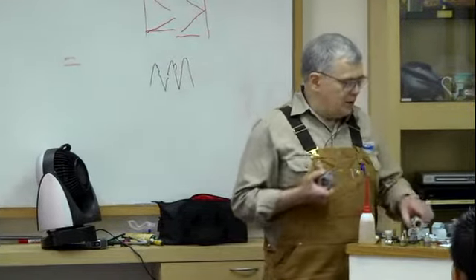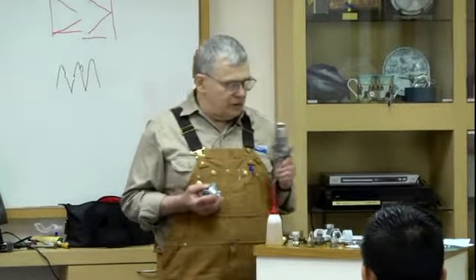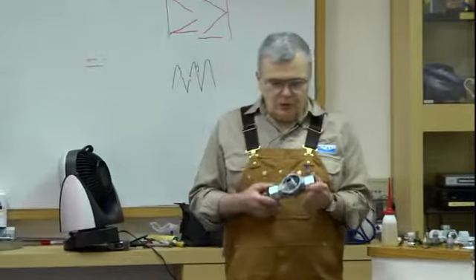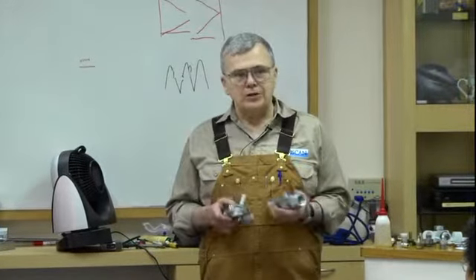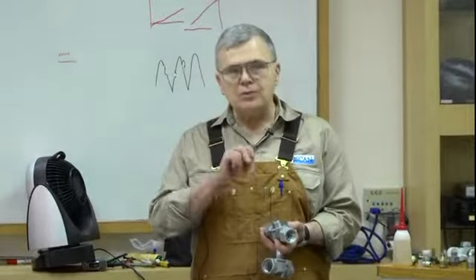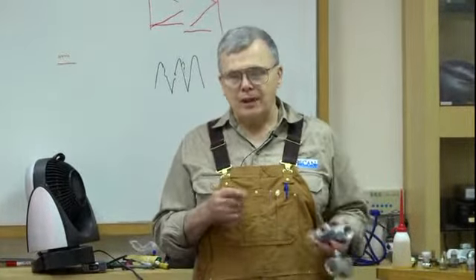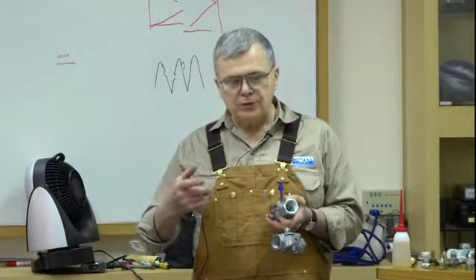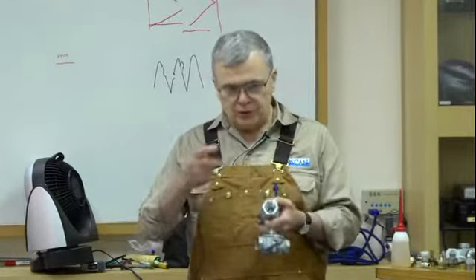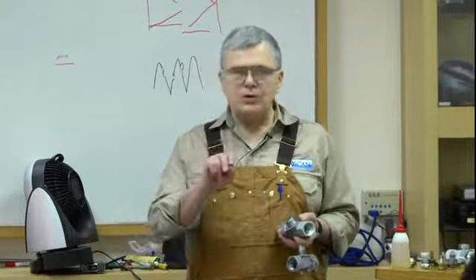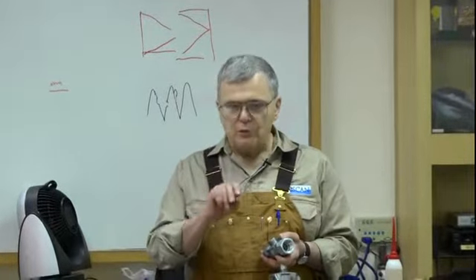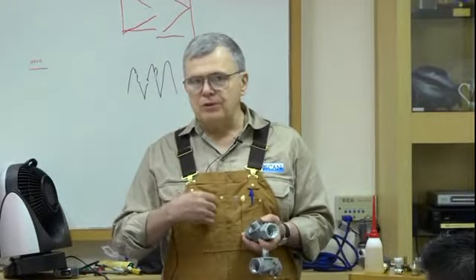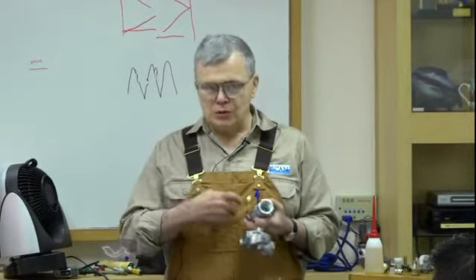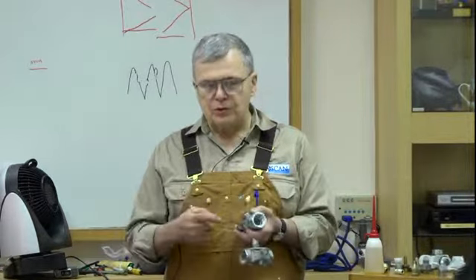The castings on the ends of the sensor, on the inlet side, we put on what we call a flow homogenizer. The canister inside the flow homogenizer, there's a tube with a bunch of holes in it. When fuel comes through the fuel line, there's a lot of turbulence with it. When you force it through openings or through small sections of tubes, it causes the flow to be more laminar. That means it's a straighter flow. There's less turbulence with it.